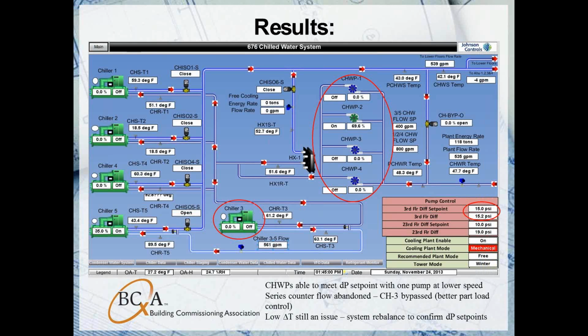Here's a screenshot of the new Johnson Controls BAS graphics. After the plant controls upgrade and some functional testing were complete, we had a lot of positive results. During functional testing, we were able to track down the source of the excess chilled water flow. We found an abandoned control valve between the plant and the air handlers that was originally used for flow control. Originally the plant had constant speed pumps, and this valve was intended to modulate to meet the flow needed in the system. This valve was never demoed. It was just left in place, and eventually it failed and was allowing a lot of flow to bypass directly back to the chiller plant.